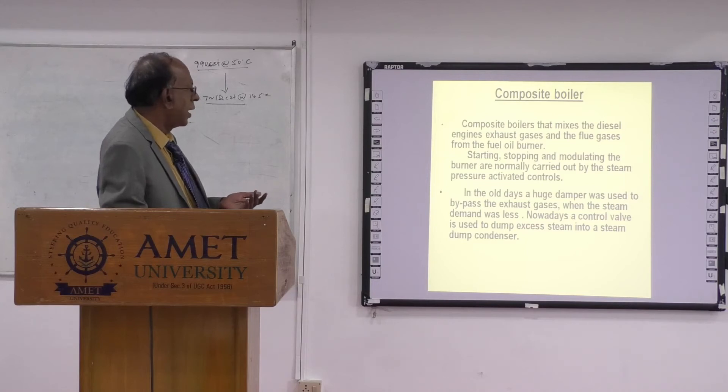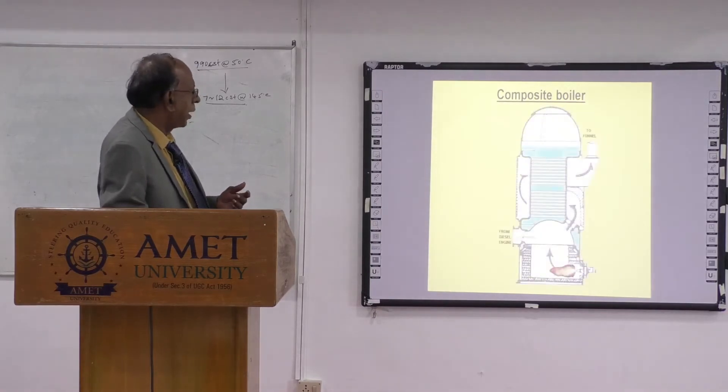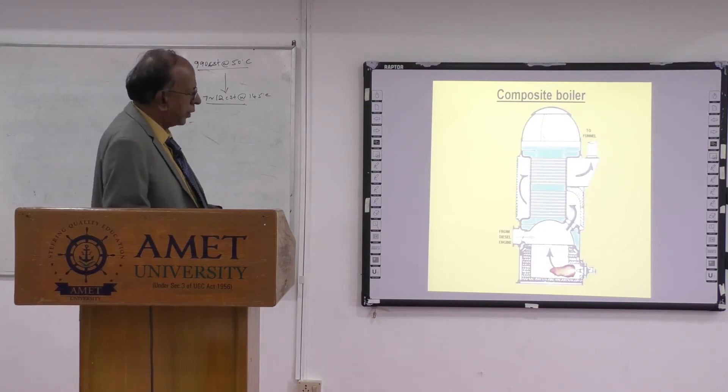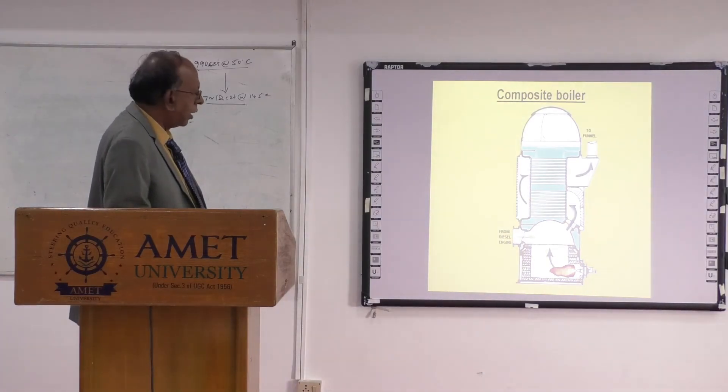In the old days, a huge damper was used to bypass exhaust gases when steam demand was less. Nowadays, a control valve is used to dump excess steam to a steam condenser. The composite boiler system works like this: you have a furnace, and you burn oil in it. From the diesel main engine, exhaust gas also comes through the tubes in a double pass — one pass and a second pass — then it goes to the bottom.